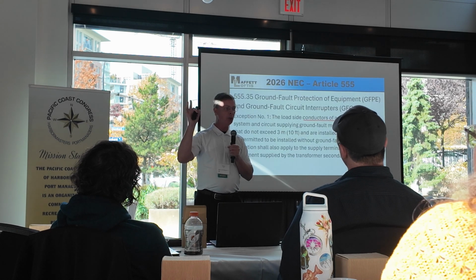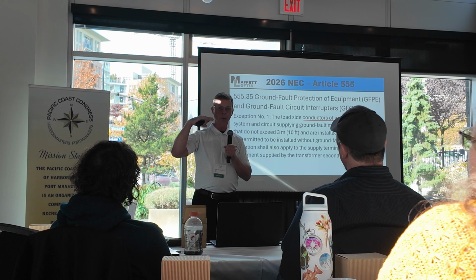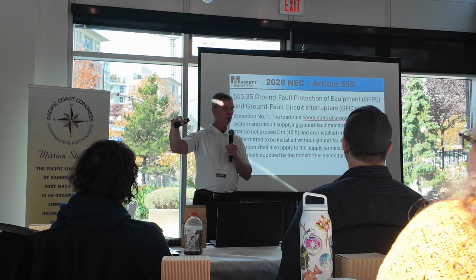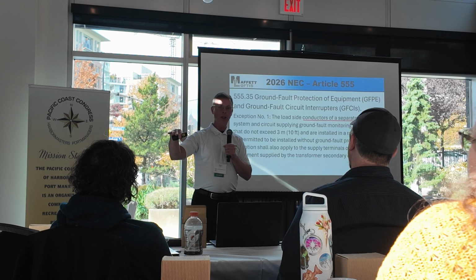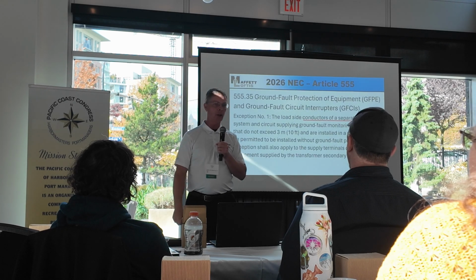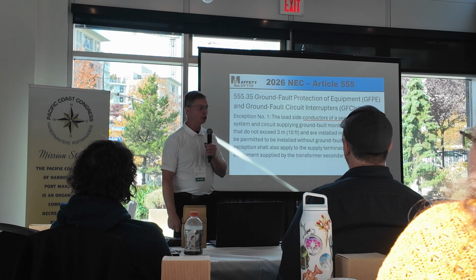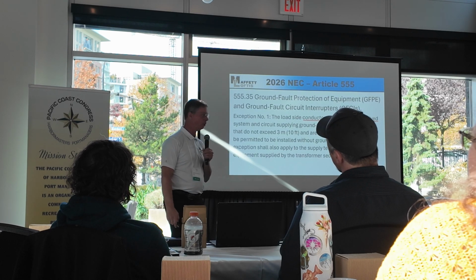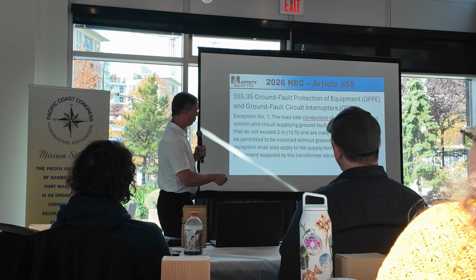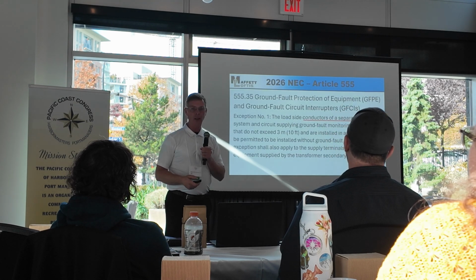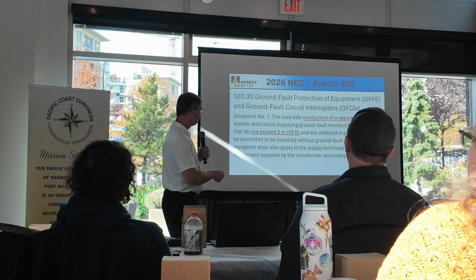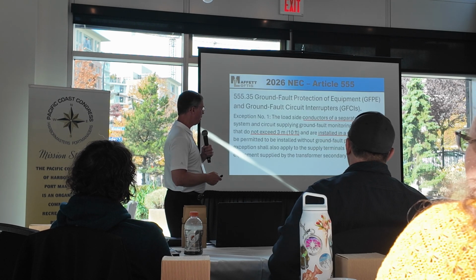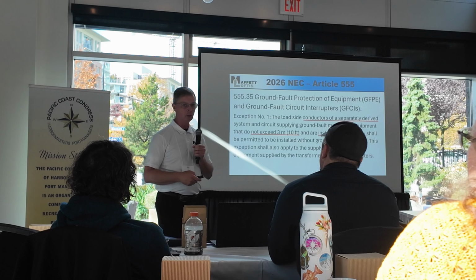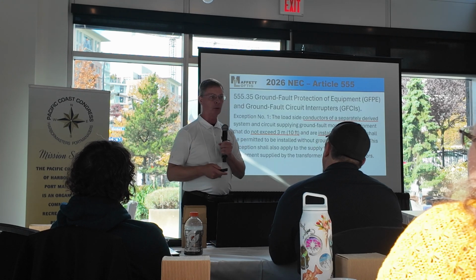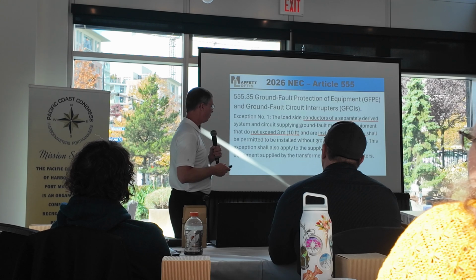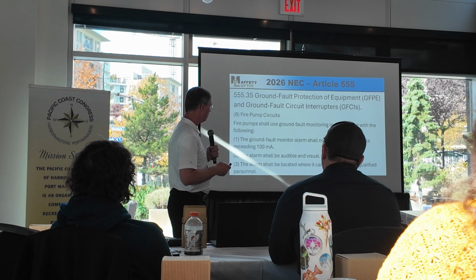I'm having actually several projects having to put emergency lighting on docks that are covered to be able to egress. So if the power goes off, battery operated lights will come on for 90 minutes to help people egress off the dock safely. And there's state jurisdictions that are requiring that throughout some of the states that I'm doing projects in. But it's very difficult to put GFPE on an inverter. So as long as that conductor is no more than 10 feet and installed in a raceway, we don't have to put GFPE on it. So it helps me as an engineer to be able to install these systems and do it very safely still. But that can be installed without GFPE.